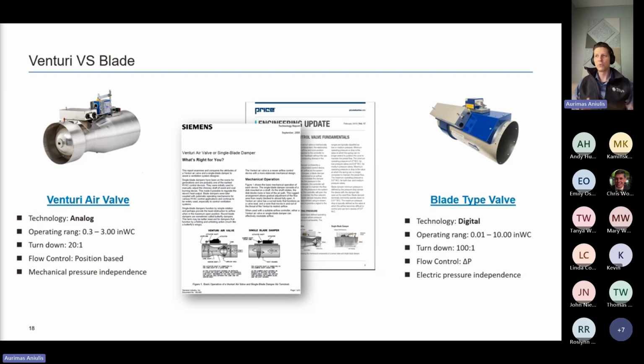They don't care about debris or chemicals. As long as the metal and the coatings on the metal can withstand corrosion, that thing is solid. It's been around for 50 years, and it'll continue to be the go-to standard for fume exhaust and laboratory exhaust air valves. Blade air valves is something that came in the industry about 15 years ago.